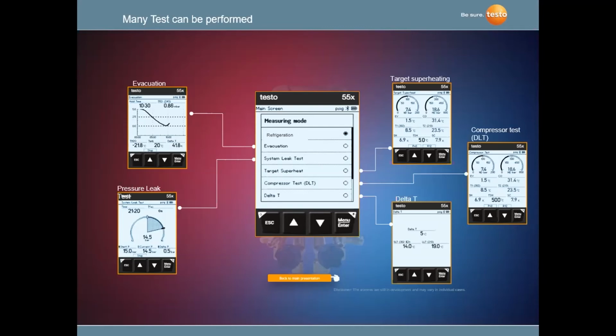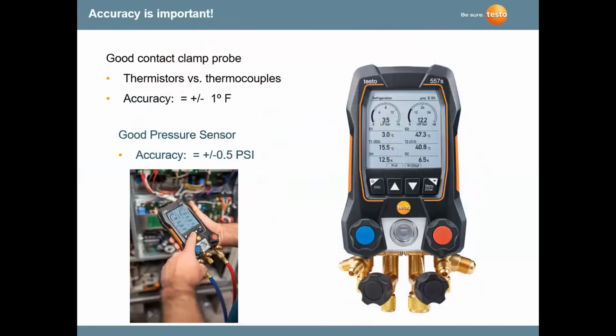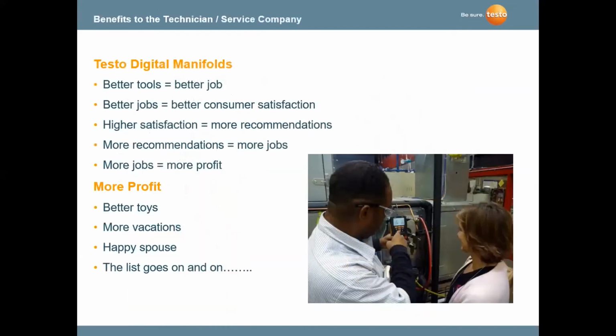Pressure leak test is a positive pressure leak test using nitrogen. Again, very accurate method of doing a nitrogen test on your system. Differential pressure. A compressor test is using three wireless probes, one on the discharge line of the compressor. Again, it's all about the accuracy, guys. Plus or minus 1 degree Fahrenheit on thermistors. NTC probes have an accuracy of plus or minus 1 degree Fahrenheit. Thermocouples are a little bit higher. Plus, thermocouples need to be calibrated periodically. Accuracy of pressure sensors is plus or minus 0.5 psi instead of 3-4 psi.